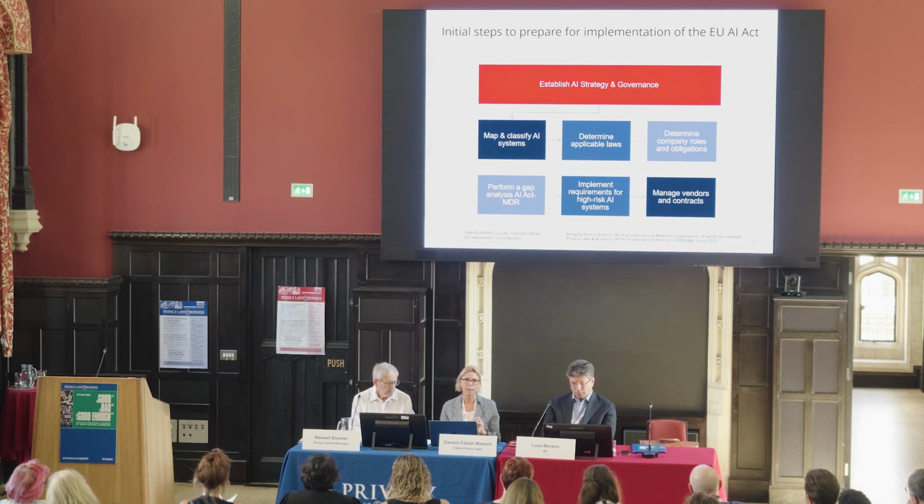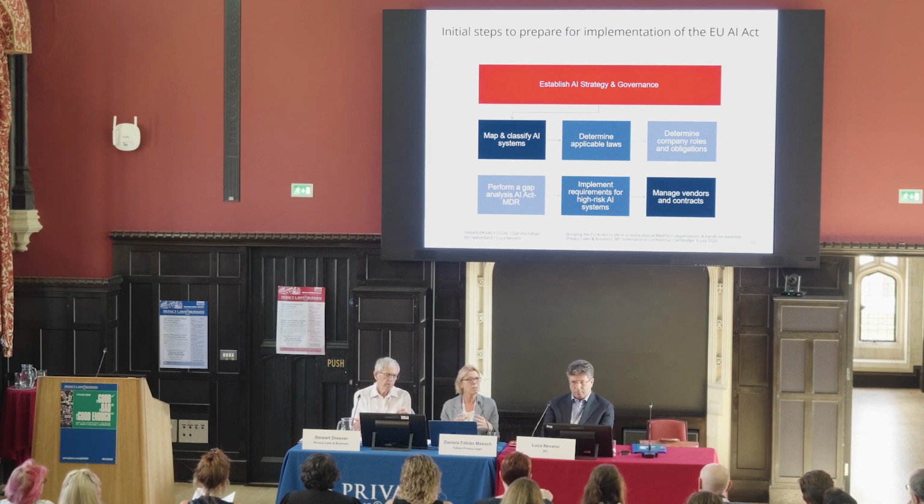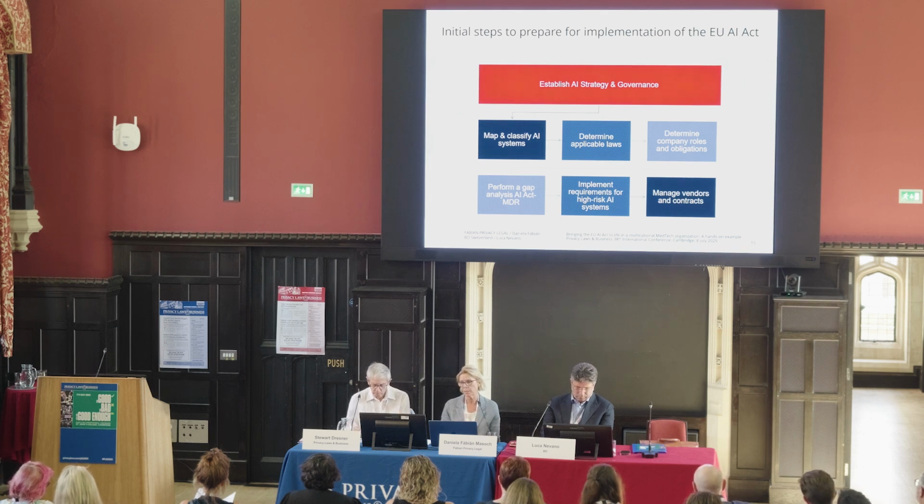For the specific Annex 1, so AI-based medical devices, it's also important to perform a gap analysis to see where are the overlaps and where are the differences. Because there are a lot of overlaps and commonalities with the MDR and the ISO standards. And it is important to have a good understanding of this, to be able to then integrate the processes. And then, of course, the implementation of the requirements needs to be done.